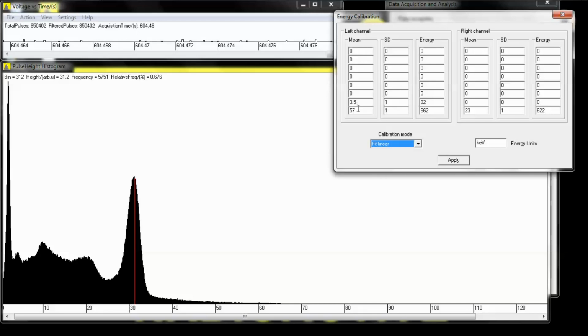And what you're going to do is write the mean. This is the centroid of the peak. This is kind of like the center part, the highest part. It's not actually the highest. It's statistically the mean of the peak. You're going to put in the standard deviation of the peak. I believe it's the first standard deviation it's looking for. I usually leave this as 1 because I'm not actually attempting to do my calibrations per se with this unit. I pretty much can pick out most of these by eyesight, but you can calculate the standard deviations for this. I'll go into that in more detail when I do a video about how to detect isotopes and everything like that. This video is just the basics of showing you how to use the software. So you can set that as 1 to start with, or you can set it correctly when you know the actual standard deviations for those particular energies.